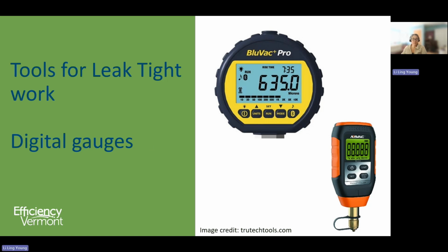Digital gauges. The most important thing about digital gauges is they're really accurate. If you're pulling a vacuum with your analog manifold gauge set, you don't know anything about how deep your vacuum is. But there are also some actual refrigerant leak prevention benefits of these gauges as well. The micron gauge or vacuum gauge can help you detect small leaks, and most importantly, it can show whether the vacuum loss you see is due to moisture in the system or a leak.